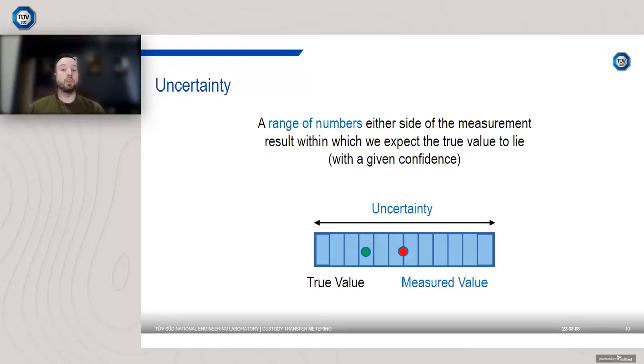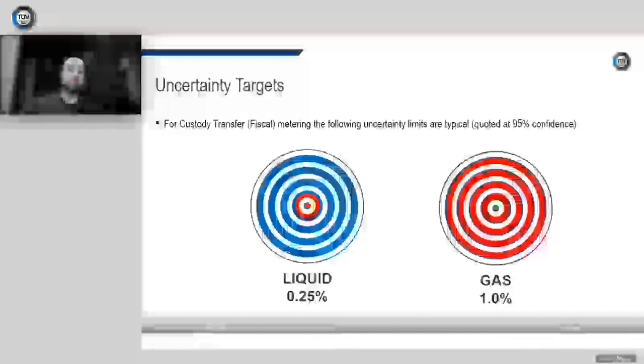The confidence is basically the likelihood that the true value will lie within that uncertainty range. So whenever you see a measurement result stated, it needs to have the measured value, it needs to have the uncertainty, and it needs to have the confidence factor. It's important again to make the distinction between accuracy and uncertainty. Accuracy is a qualitative term, so you can't assign a value to accuracy. The two are often confused, but if you want to quantify things, you really need to state an uncertainty.